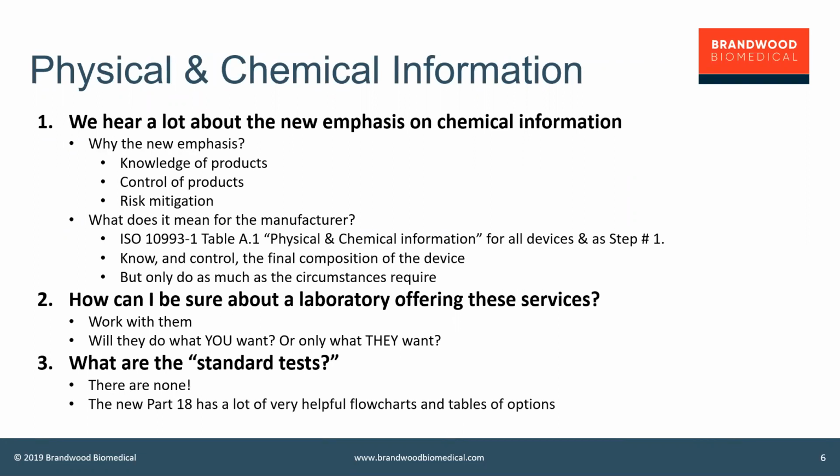And the new Part 18 is going to have a lot of very helpful flow charts and indeed tables of options to help in the selection of methods. Because, of course, you will have to use very different methods if your device is a ceramic to if your device was a metal, and again, a different set if your device was made from polymers. So there will be some very good toolkits, if you like, in the new Part 18. But you always have to remember why you're doing this and scale this appropriately. So you just have to do as much as the circumstances require. I really can't emphasize that strongly enough.